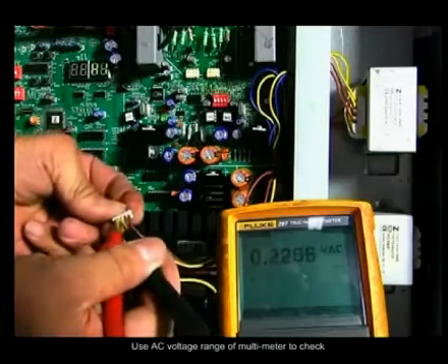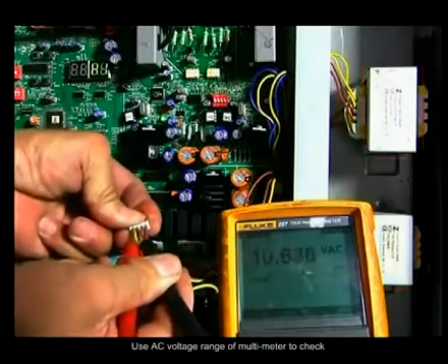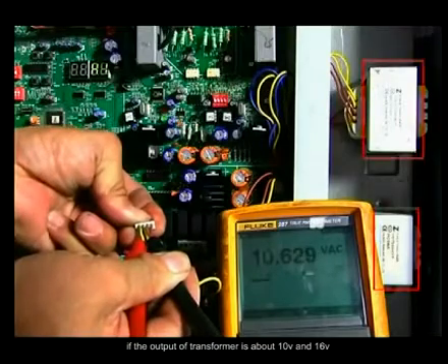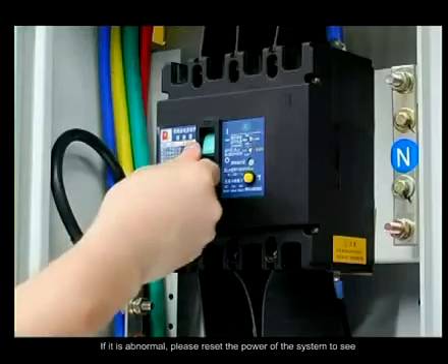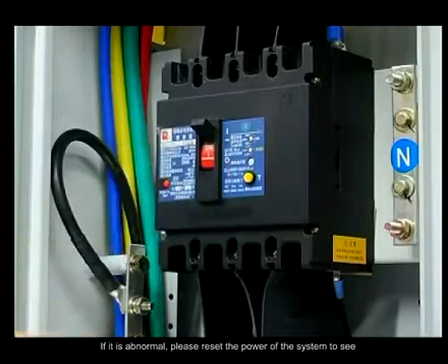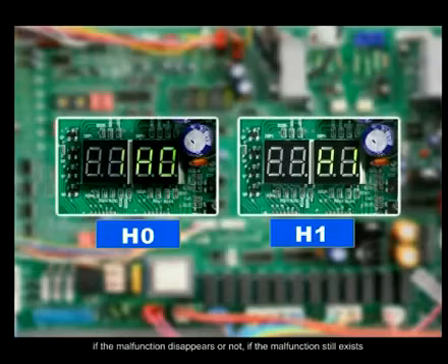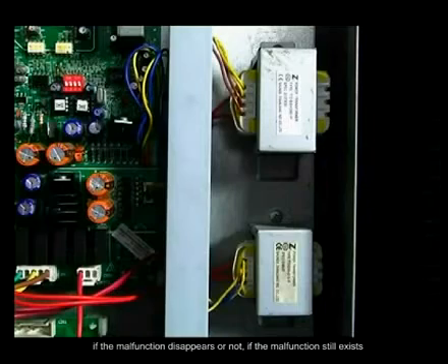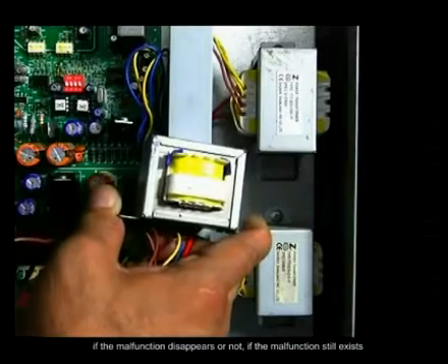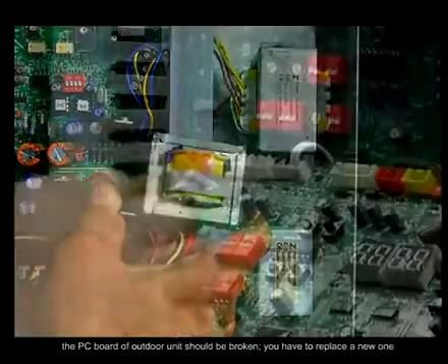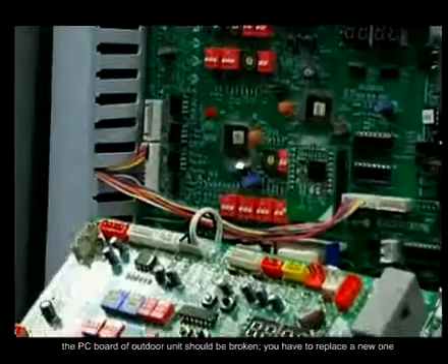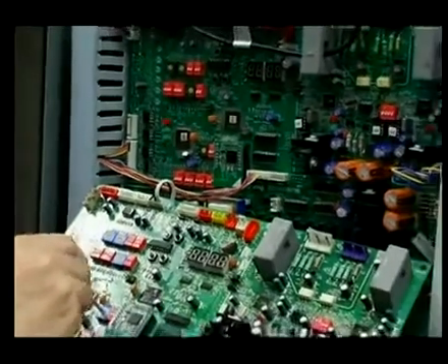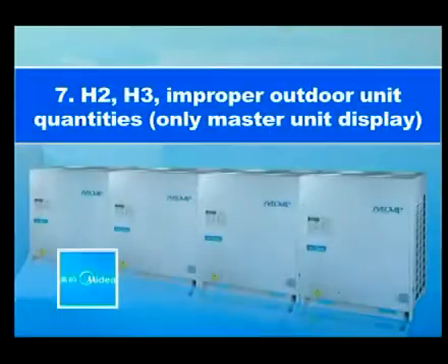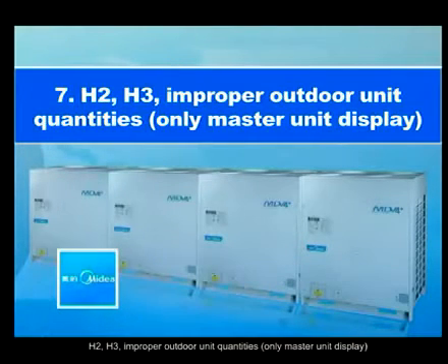Use the AC voltage range of the multimeter to check if the output of the transformer is about 10 volts and 16 volts. If it is abnormal, please reset the power of the system to see if the malfunction disappears or not. If the malfunction still exists, the PC board of the outdoor unit may be broken. You have to replace it with a new one. H2, H3, improper outdoor unit quantities. Only master unit displays.